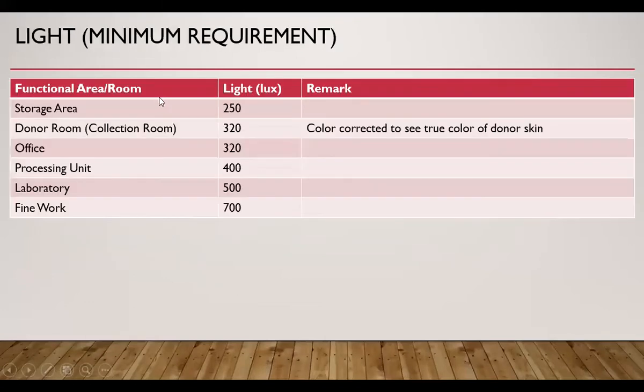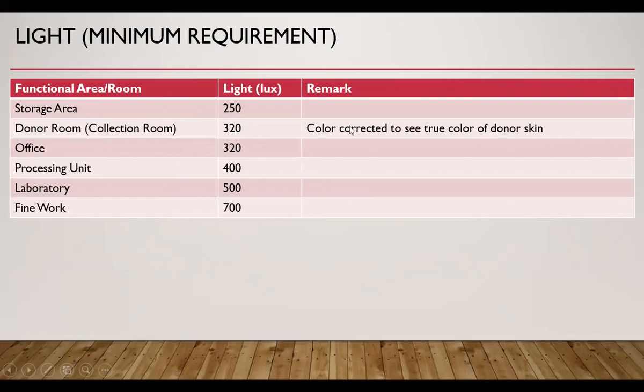For illumination requirements: the storage area requires 250 lux, fine work requires 700 lux, and laboratory work requires 500 lux. In the donor room, we need color-corrected light to see the true color of donor skin so that we can decide about donor acceptance.